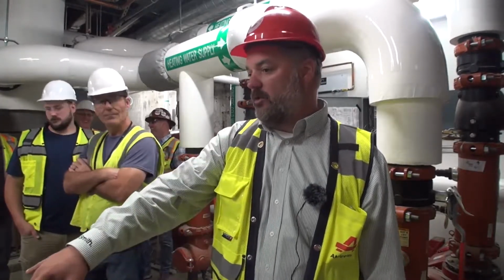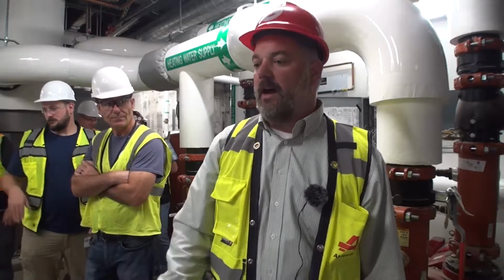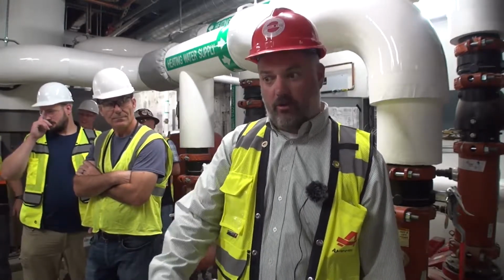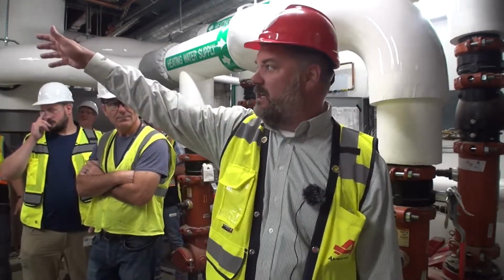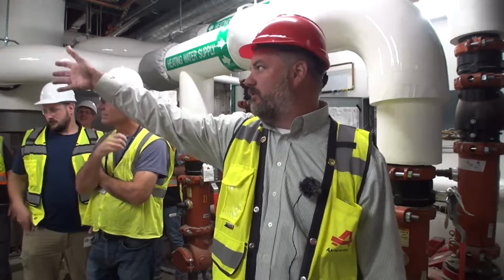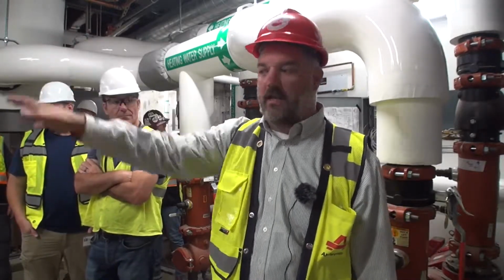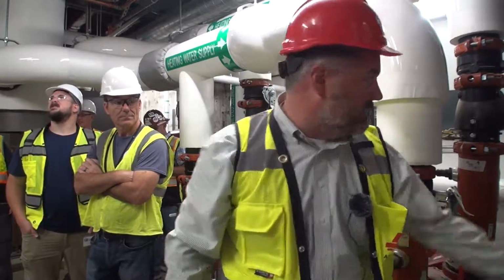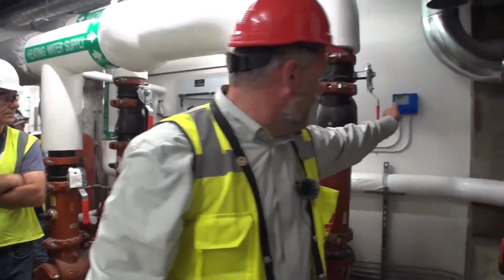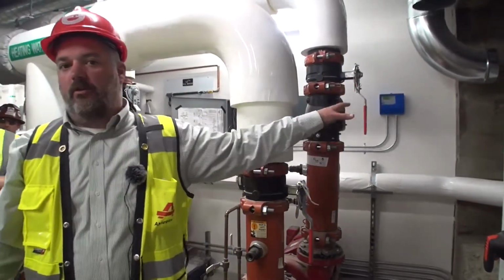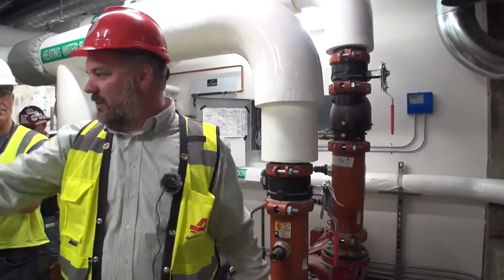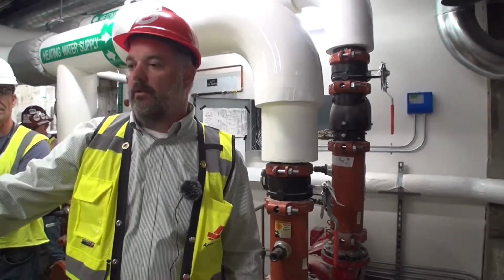We've got basically 2 hot water circulating boilers from A.O. Smith. Those are the XW1300s. We've got an HD, I do believe it's either a 42 or 48, 500-gallon storage tank that they're routed through, and then we've got a tekmar 263 2-stage boiler control that actually does the control operation of these boilers.